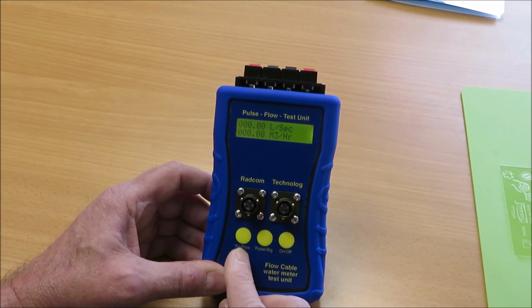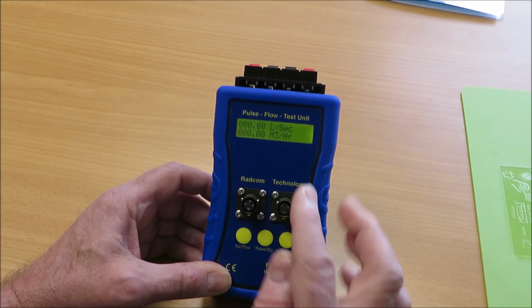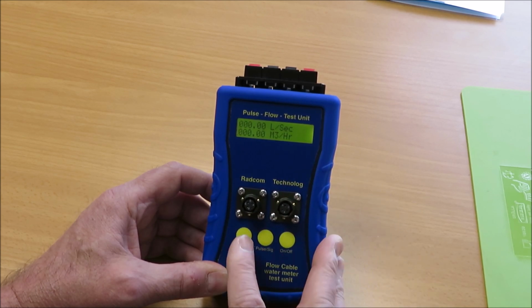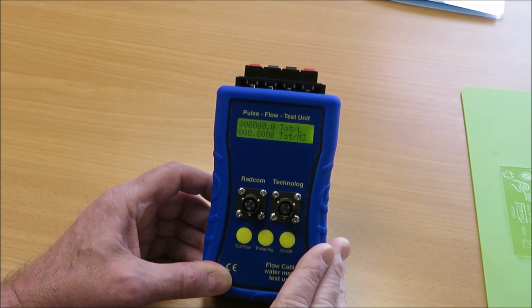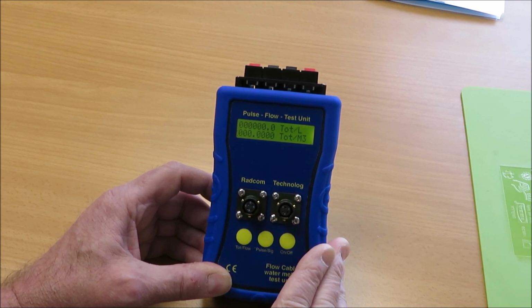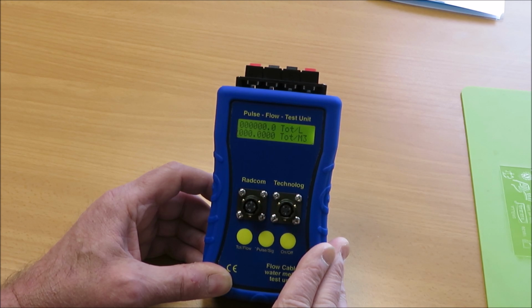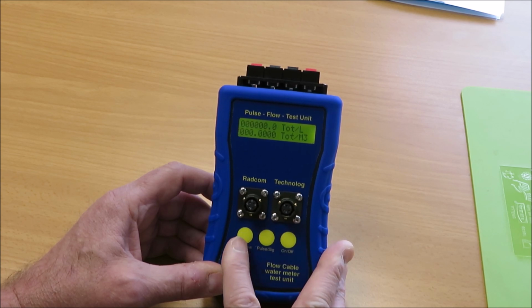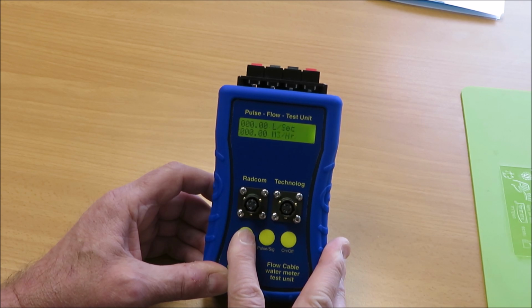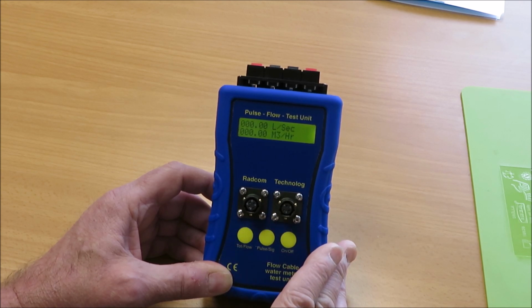The other button to the left that says total and flow literally switches between the flow rate shown in litres per second or meters cubed or a total. So if you wanted to just measure the flow through the meter for 5 minutes and then switch the water off, you would get a total value of volume of water that has gone through the meter, either in litres or in meters cubed. And if you want to go back to a flow rate, you can simply press the button there.